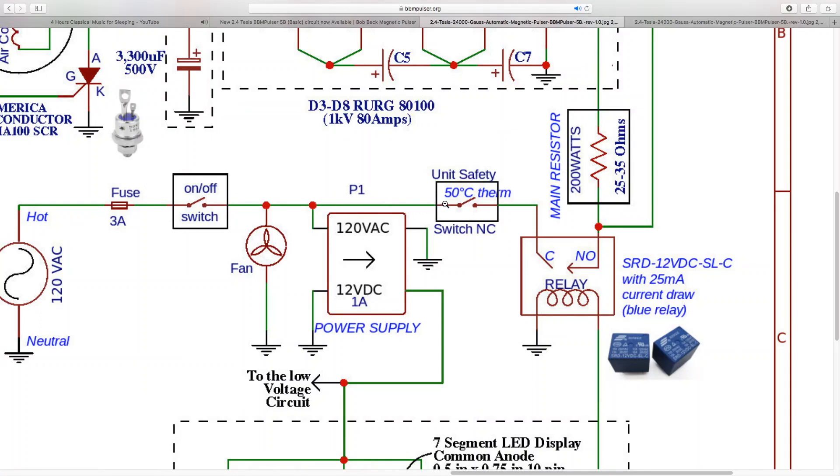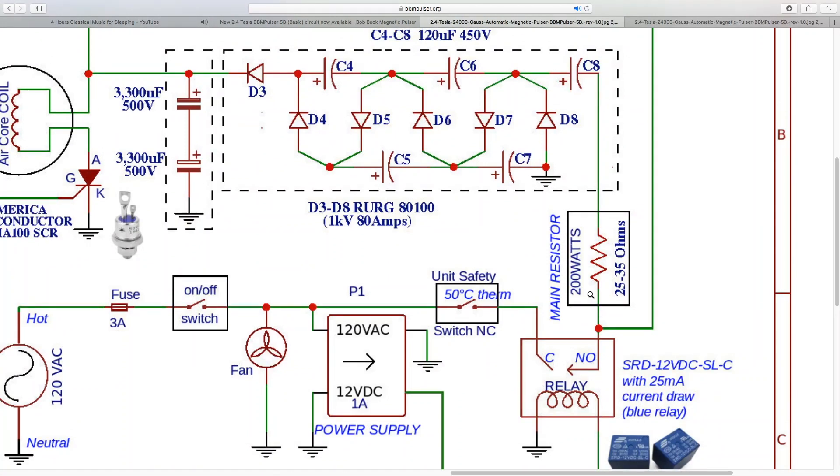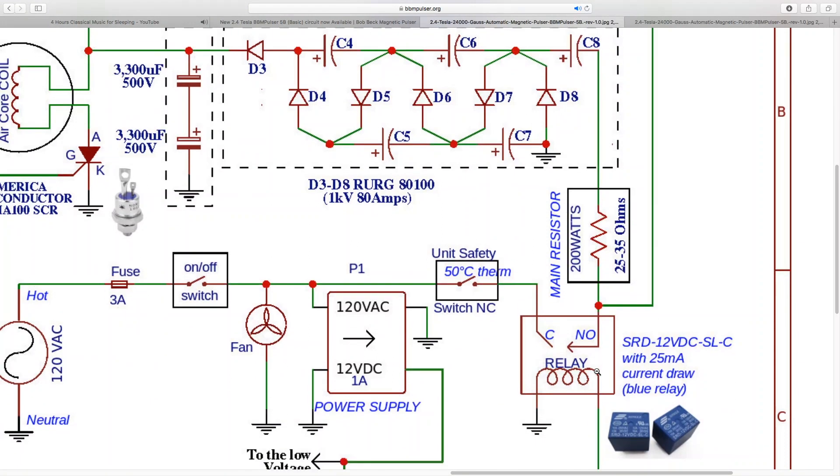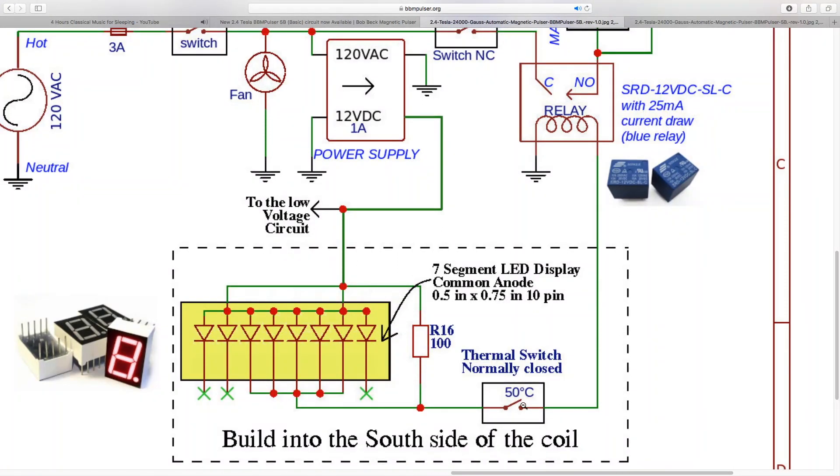After that, power is going to go into the thermal switch. This thermal switch is normally closed and it's set to trigger at 50 Celsius. Anytime internal temperature raises over 50 Celsius, this thermal switch will trigger and cut all the power to the charging circuit here.